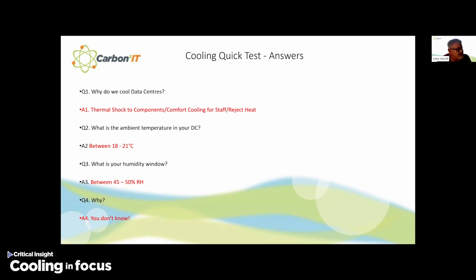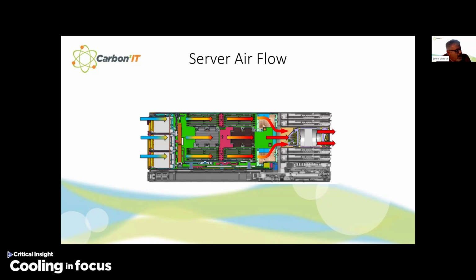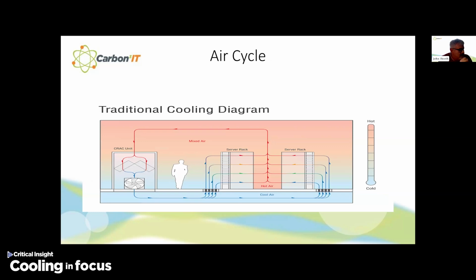So I'm now going to give you a brief lesson in cooling. There are two major heat components in a server. The first is the chip, which Jonas was talking about earlier, and they're trying to get the high temperatures on the chip away to you for your more useful services. And the second part is the transformer. So the transformer is actually transforming 220 to 240 volts AC down to the plus and minus DC voltages that are contained on the motherboard. That is a big drop down, and as such, it generates heat. And as you can see from this diagram here, we bring in cold air in the middle, we pass it across the chips and the transformer, and we expel it out the end. And that can be seen quite well in this diagram.